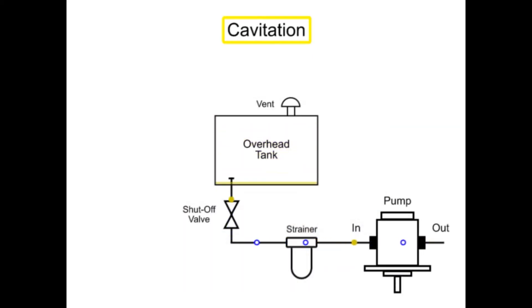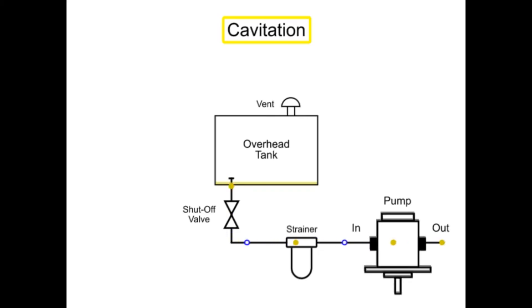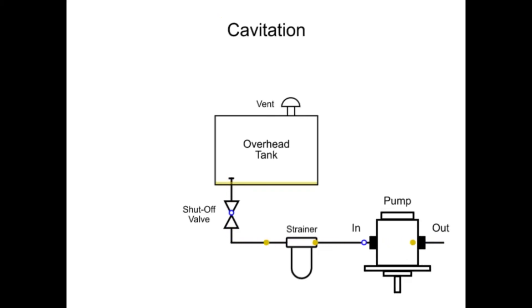Cavitation is often characterized by loud noises such as grinding, or as if there are marbles in the pump, and pitting damage to parts as material is removed by the bubbles.